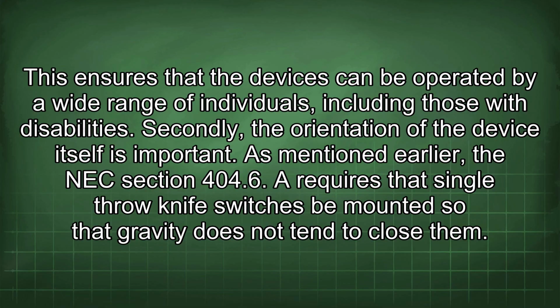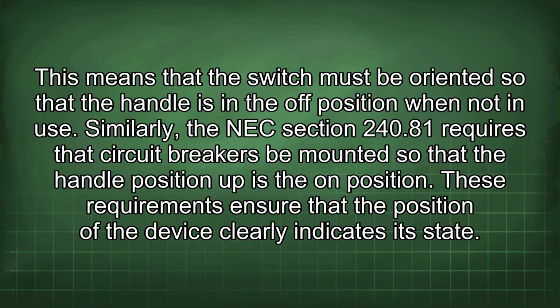As mentioned earlier, the NEC section 404.6 requires that single-throw knife switches be mounted so that gravity does not tend to close them. This means that the switch must be oriented so that the handle is in the off position when not in use. Similarly, the NEC section 240.81 requires that circuit breakers be mounted so that the handle position up is the on position. These requirements ensure that the position of the device clearly indicates its state.